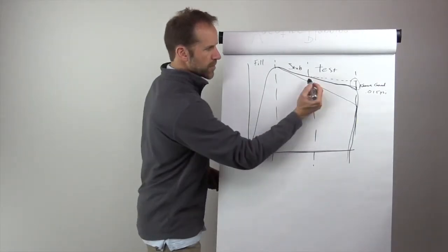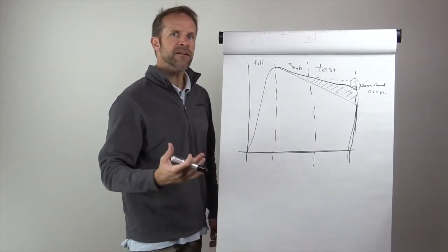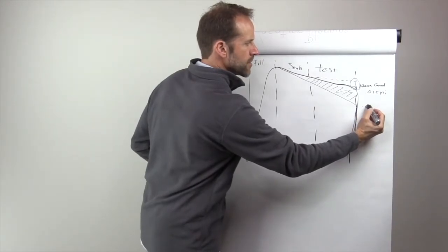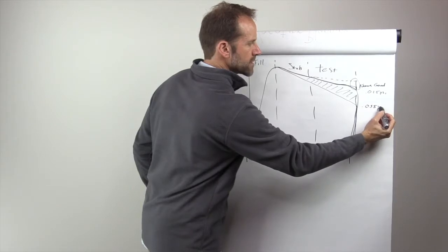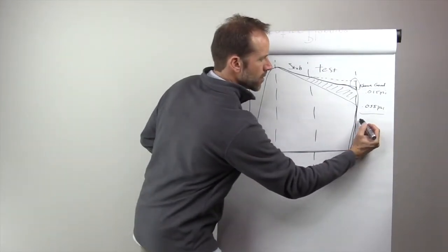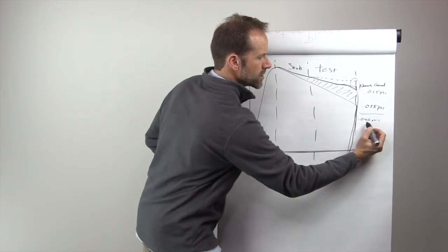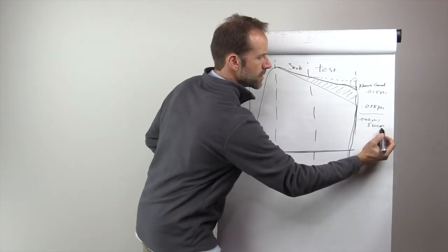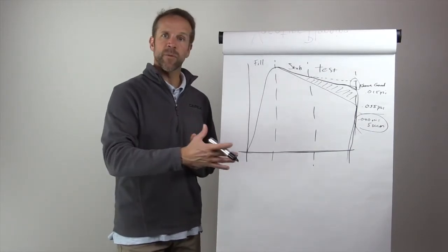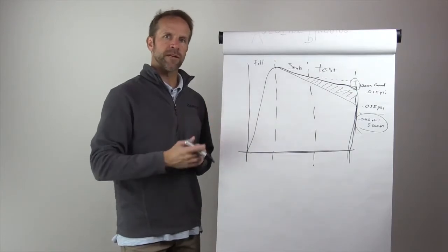This area right here represents the pressure loss as a result of the leak standard. The 5 SCCM leak standard that we introduced is represented in that pressure loss. Let's say it is 0.055 psi. So effectively, what happens with the leak test instrumentation is that if we take the difference between those two, 0.040 psi equals 5 SCCM to the instrument. So that's what it did. It established a ratio between the pressure loss and the leak standard. We've told the instrument the leak standard is this value, so it knows what to correlate that value with.